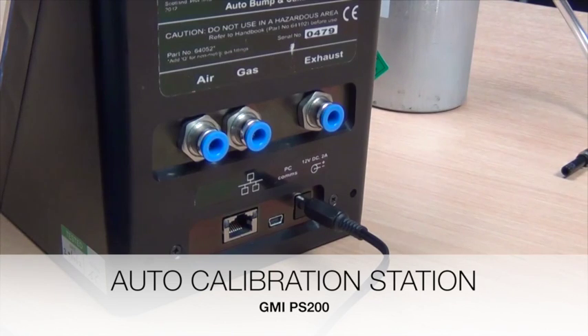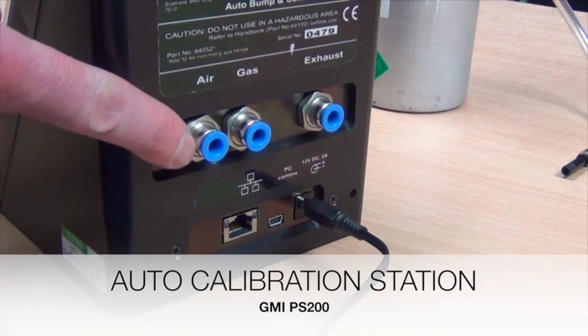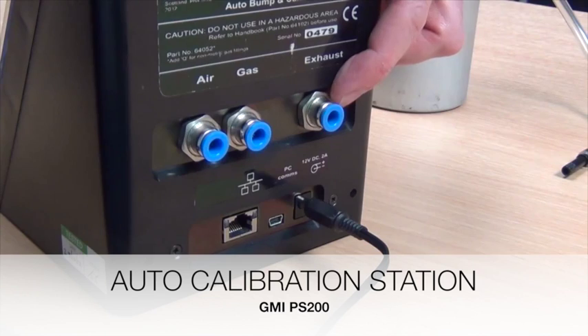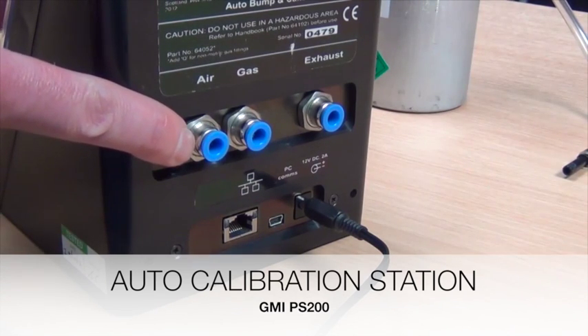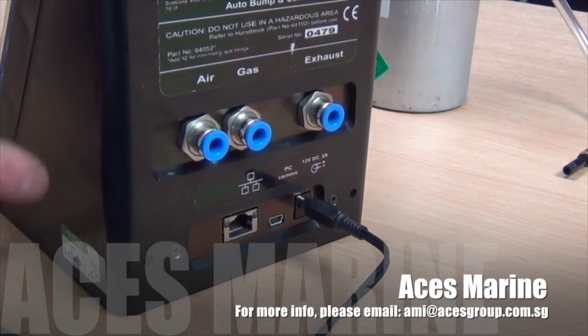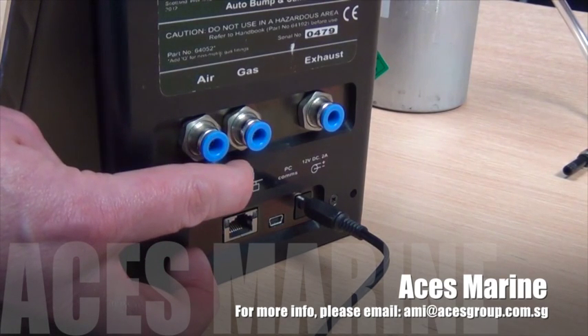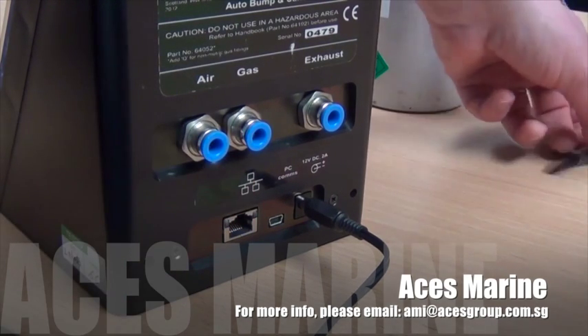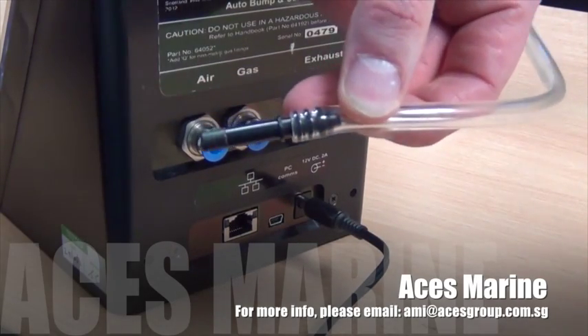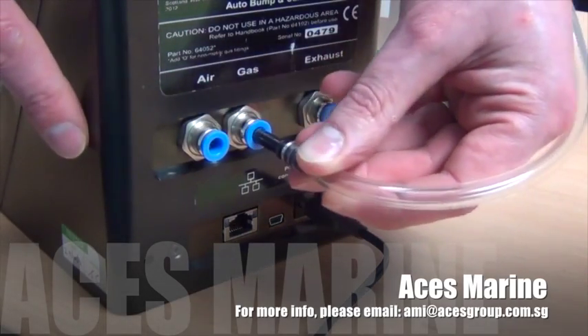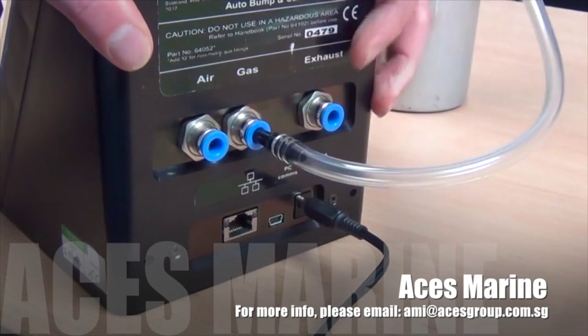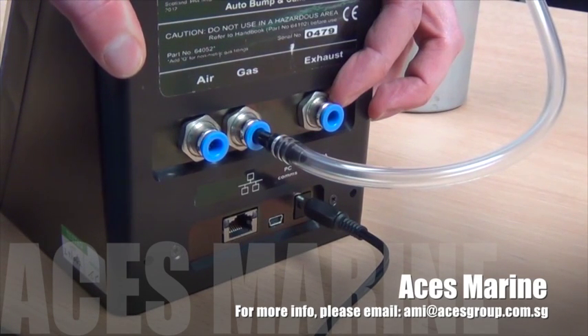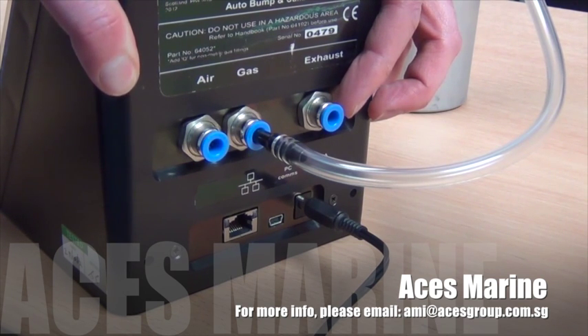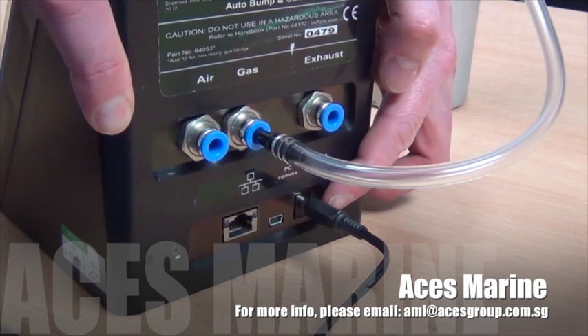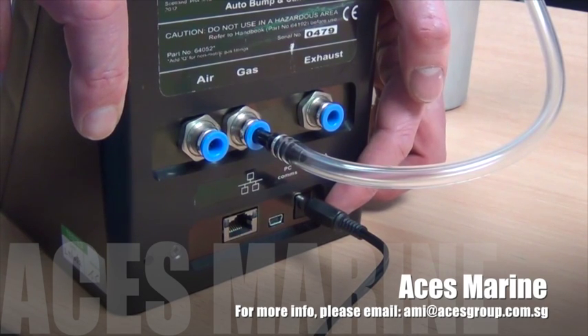So on the rear of the ABC we have air inlet, gas inlet and an exhaust. On the air inlet we can also add a hydrophobic filter. The gas inlet is the gas that has been used for the calibration. You use the barb supplied with the ABC and you push it into the quick connect. The exhaust can also have a tubing attached to ensure the gases used during the calibration are then taken away from the environment that we're in. And lastly, the power supply is then put in here.